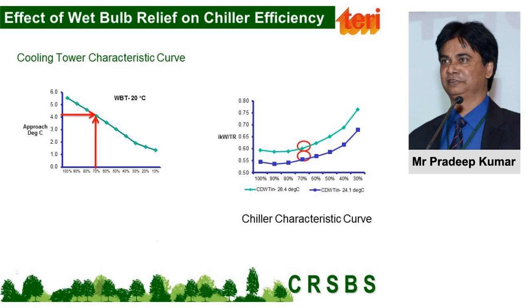And what we found when we measured the temperature of the water coming out of the cooling tower, what we call the cooling water temperature, entering into the condenser was somewhere around 28.4 degree. And if you compare, let's say for the same supply chilled water temperature, this line shows the condenser water in at 28.4 degree, and the bottom one is at 24, which is possible because of this wet bulb. So we were losing somewhere around 0.05 kilowatt per ton. So per hour we can always work out. So this is the second thing we have done.